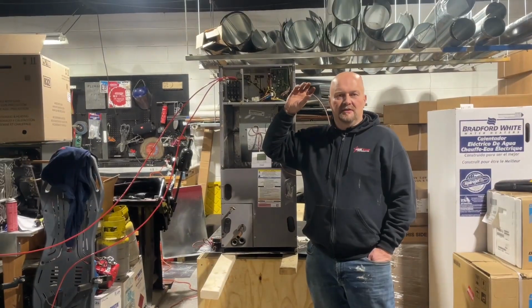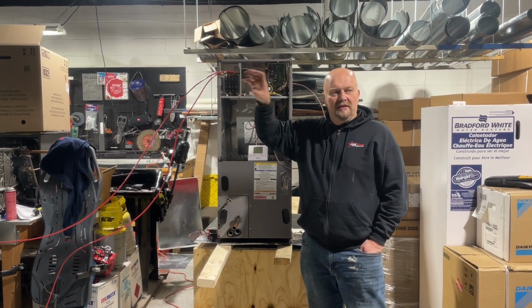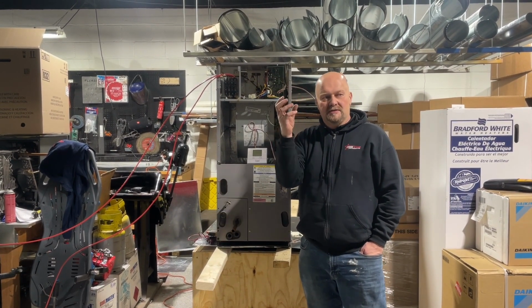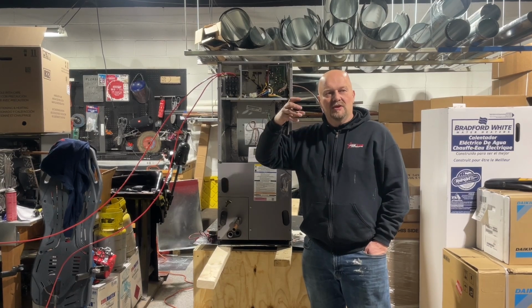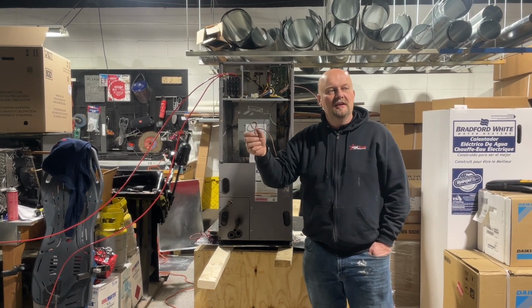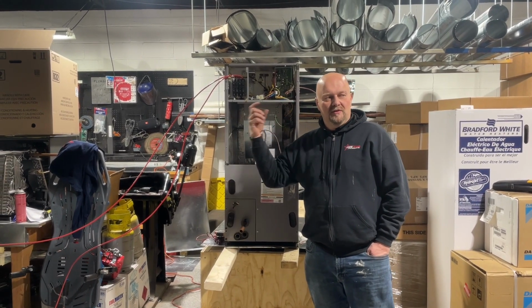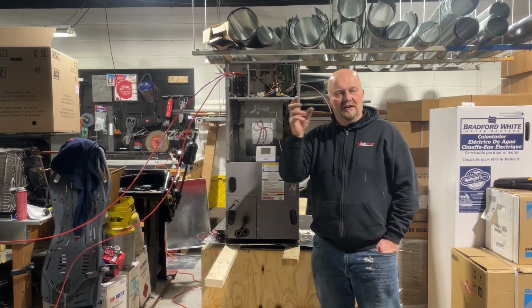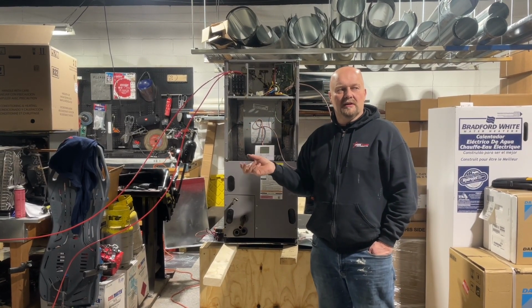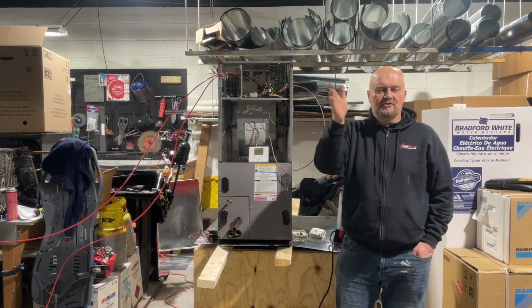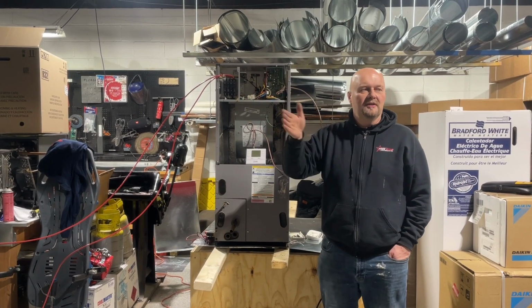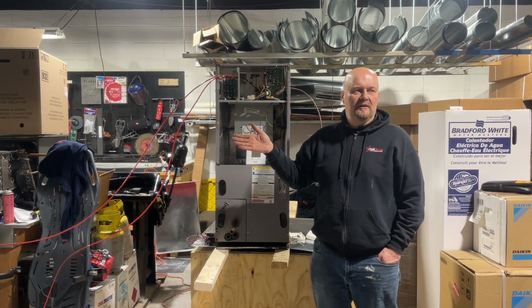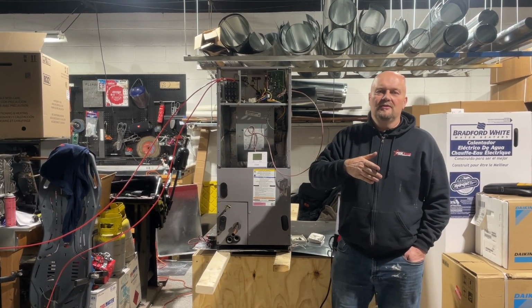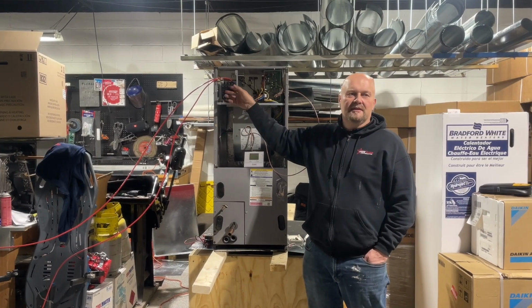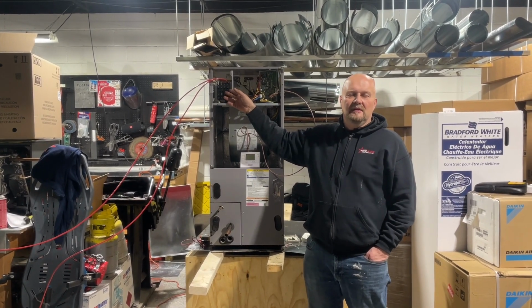Most of the time you could trip the circuit breaker. You can have nuisance trips. So the first stage will engage, and that part will start warming up the sequencer. Then the sequencer turns on second, and it starts to warm up with 24 volts, then a third sequencer, and they're spaced about 2 to 3 minutes apart. So then you turn on all your strips within like a 9-minute time frame. You do that so you don't trip the circuit breakers needlessly. That's the only reason.